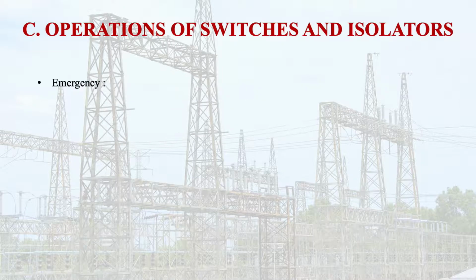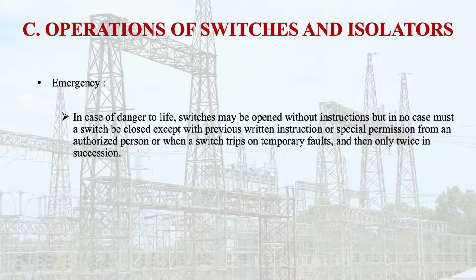Now, emergency. In case of an emergency while working with high voltages, what are the safety instructions? In case of danger to life, switches may be opened without instructions, but in no case must a switch be closed except with the previous written instructions or special permission from an authorized person, or when a switch trips on temporary faults, and then only twice in succession.